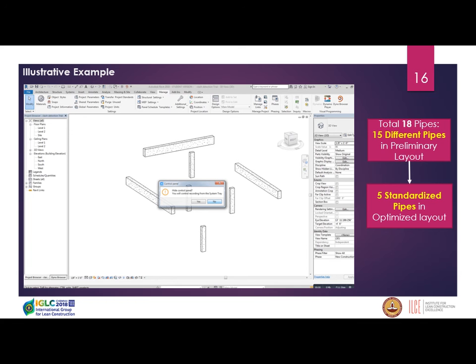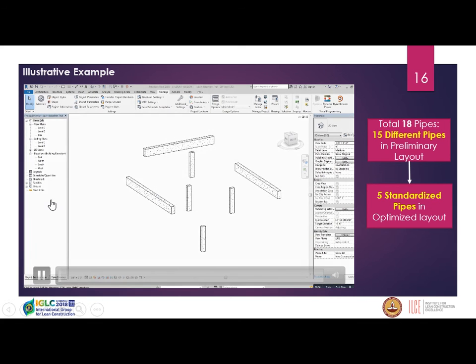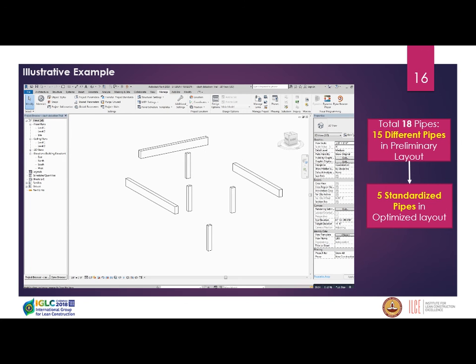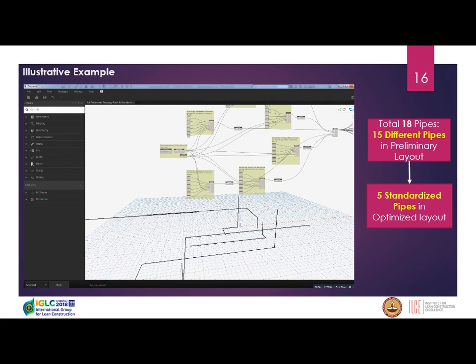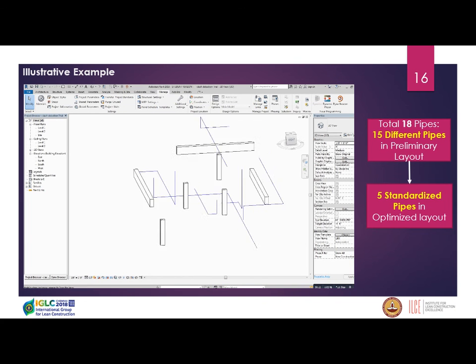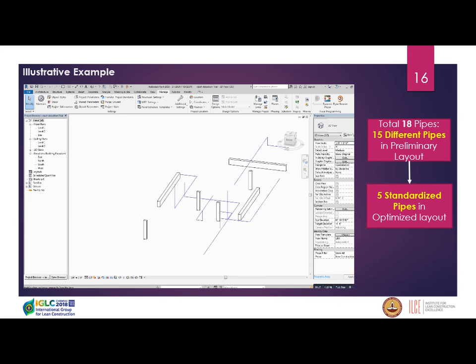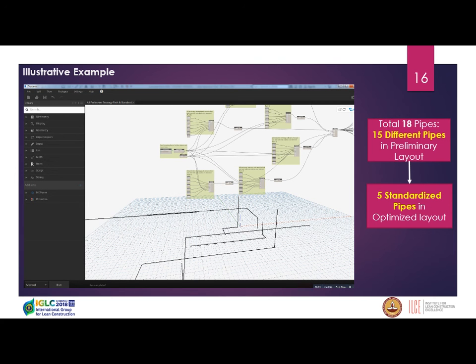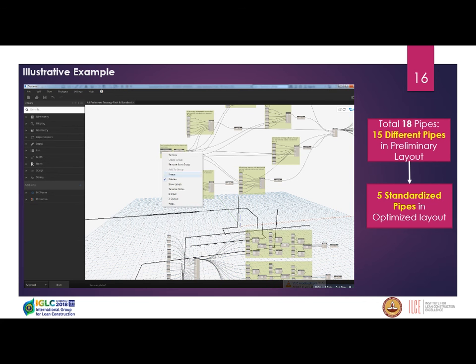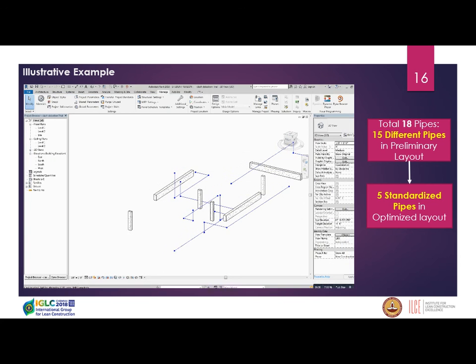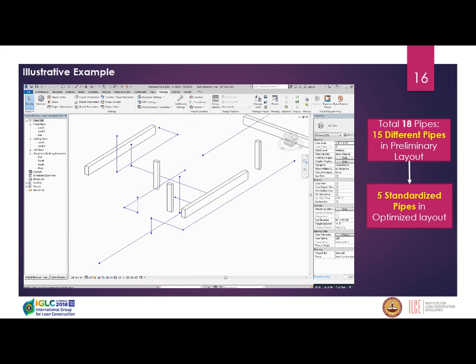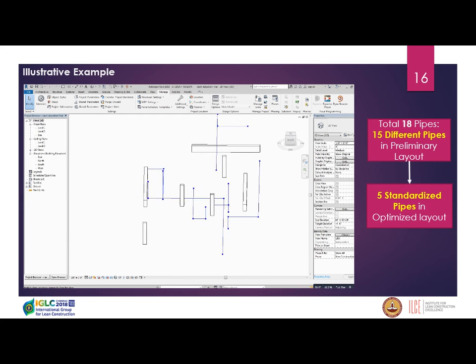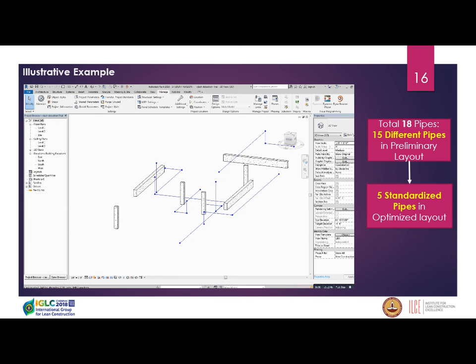Here is an example I tried. With a list of objects including columns and beams, I generated a preliminary clash-free route using the perimeter strategy. It has a total of 18 pipes, of which 15 are different types having different sizes and shapes. Applying the k-means clustering algorithm produces an optimized layout using only five standardized pipes — those 15 different pipes have been converted to five standardized pipes. After performing the design check and loading service condition check, this is the final optimized layout.